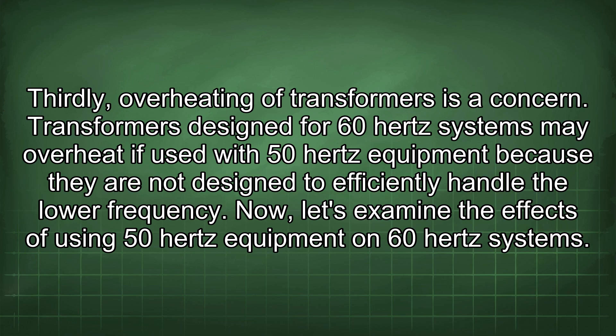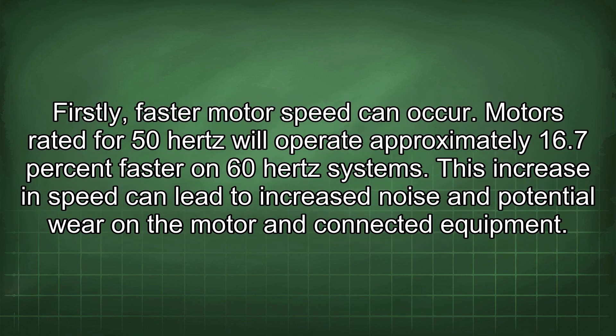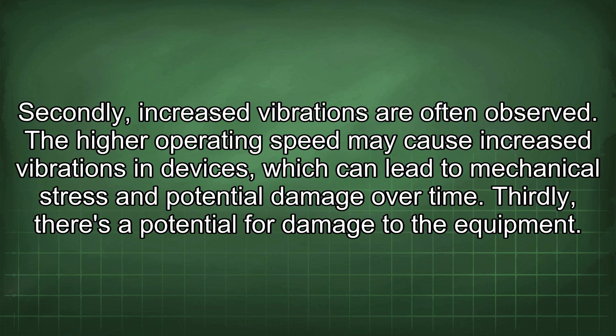Now let's examine the effects of using 50Hz equipment on 60Hz systems. Firstly, faster motor speed can occur — motors rated for 50Hz will operate approximately 16.7% faster on 60Hz systems. This increase in speed can lead to increased noise and potential wear on the motor and connected equipment. Secondly, increased vibrations are often observed, as the higher operating speed may cause mechanical stress and potential damage over time.